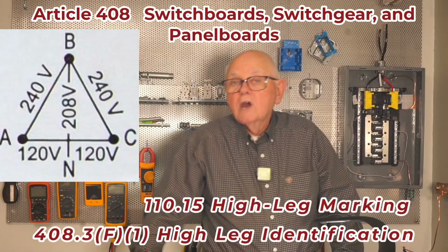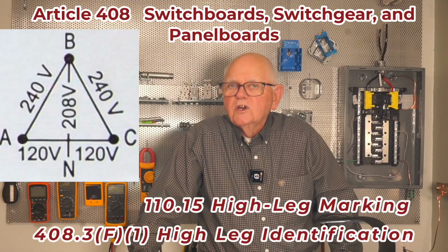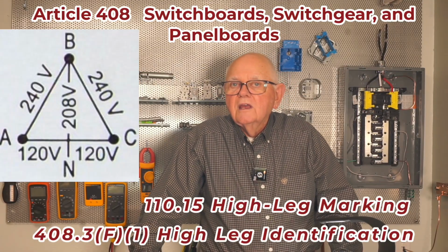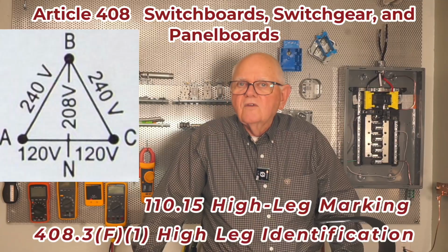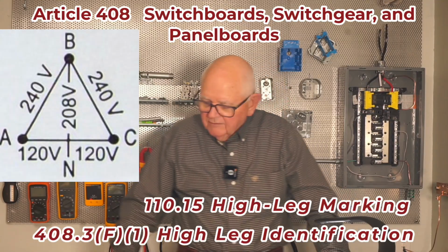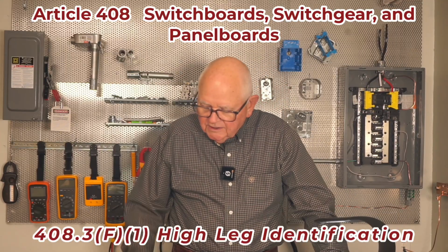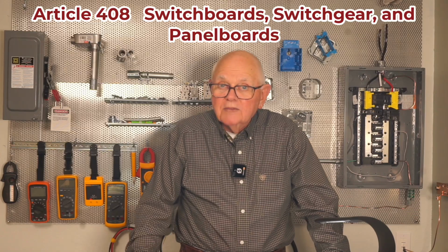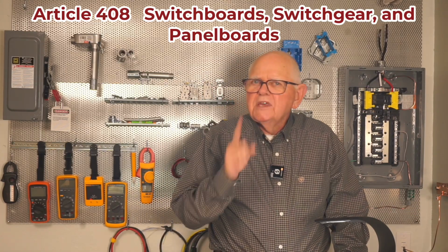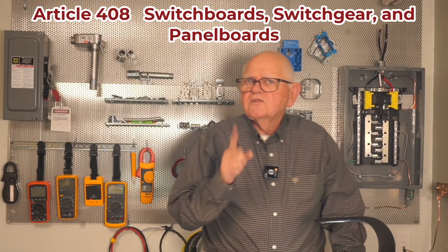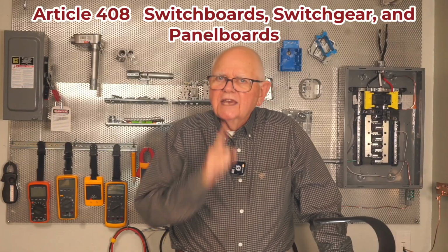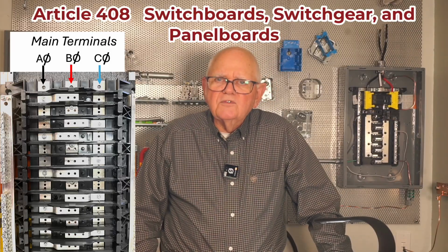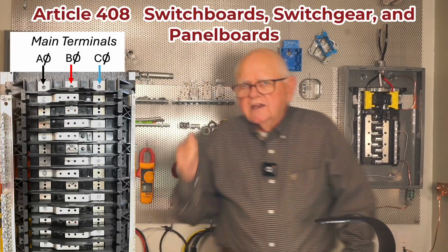So for the high leg marking requirement, we go back to 110.15 in addition to 408.3 and find additional information on that. So that's an important one for us. And the high leg, by the way, must always be B phase on the 3-phase panel board. Let's take a look at the 3-phase panel board and see what that looks like on the inside then.